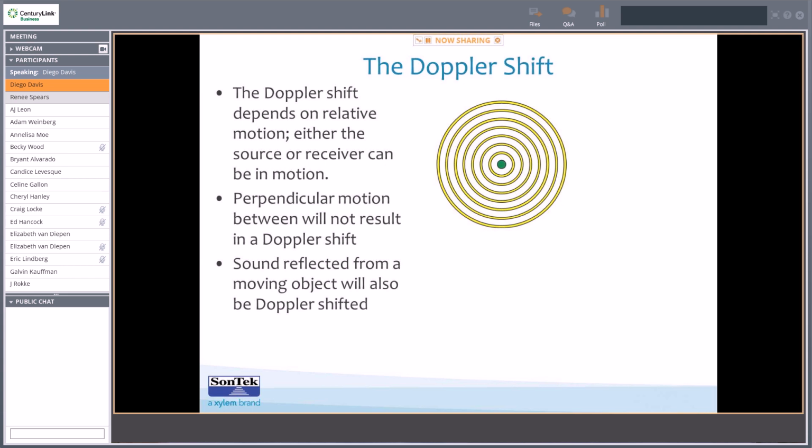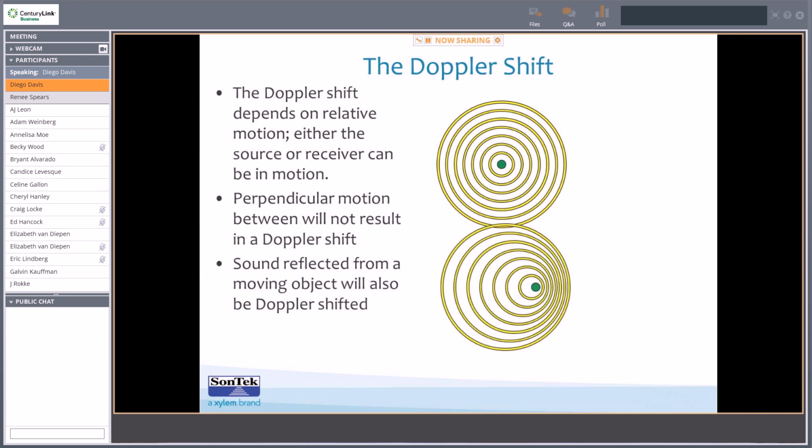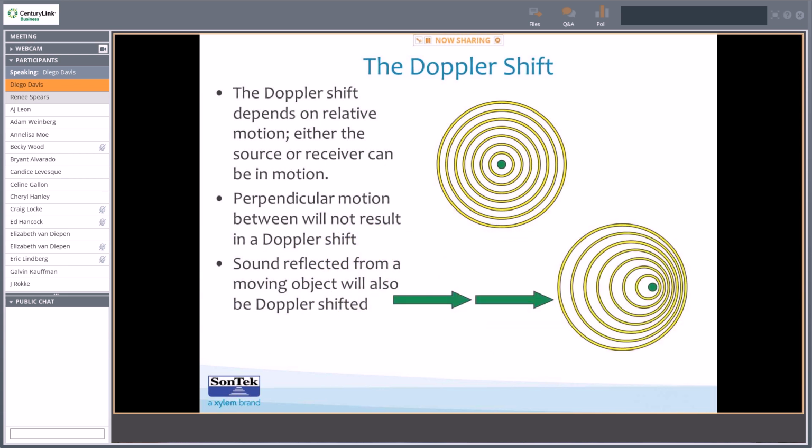And so what happens in a Doppler shift is essentially we send out a small frequency of sound, and it reflects off these particles, and we wait to listen for that. And when we wait to listen, we're able to measure a Doppler shift. So just as you're seeing here, that object is going to show that it's biasing in a certain direction, and that direction and velocity can be measured and then calculated into a mean velocity for that particular transducer.